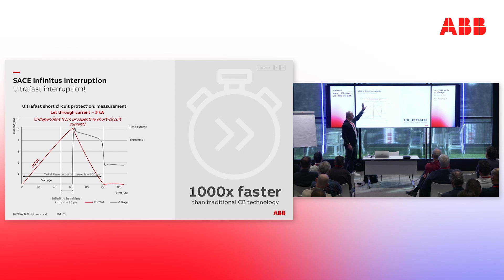One important topic is how do we achieve selectivity. I touched on this and won't go into great detail, but normally we talk about selectivity between neighboring sectors or between the big sectors. For example, to help with the marine example, here you would have different drives connected to the DC grid via electromechanical switches or fused contactors. If you have a fault here, there is no selectivity between them.